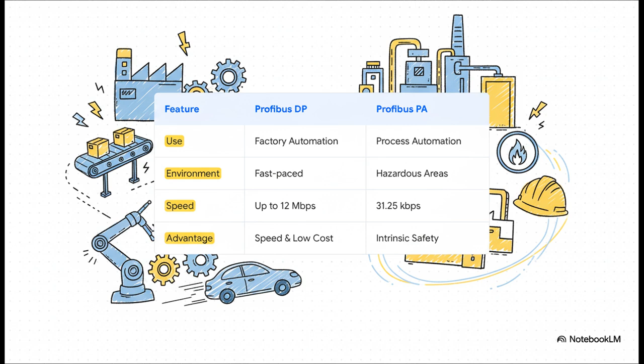Get this, it can deliver both power and data over the exact same two wires. But here's the genius part, the power level is kept so low that it physically cannot create a spark. This makes it intrinsically safe for use in places where there might be explosive gases or dust. For installation, this is a massive deal. You don't need all that expensive, heavy-duty explosion-proof conduit and wiring. The cost savings are just huge.